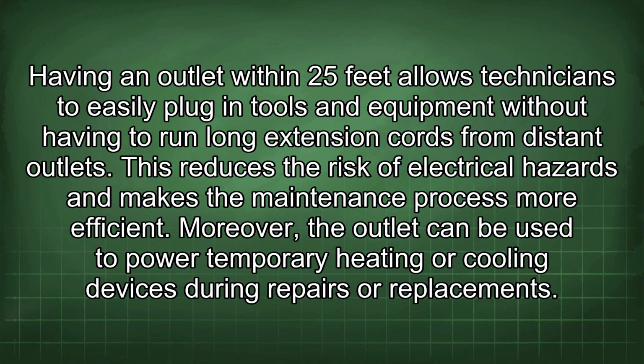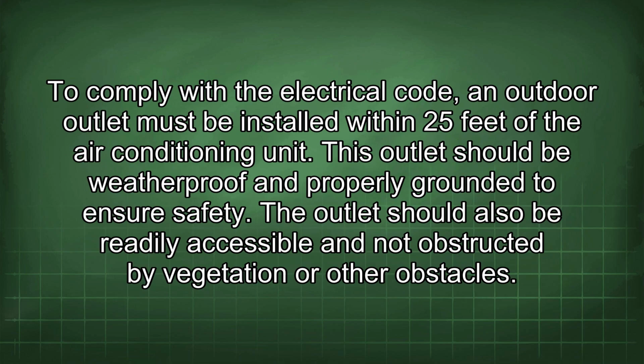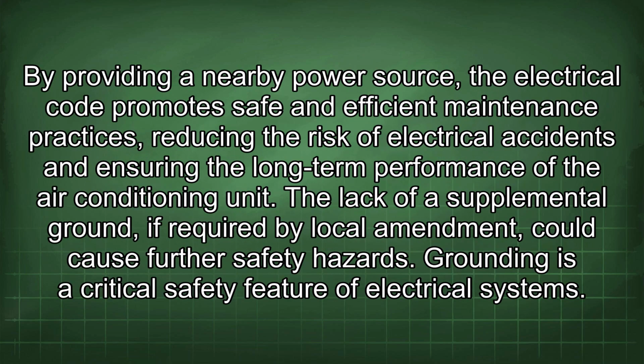Moreover, the outlet can be used to power temporary heating or cooling devices during repairs or replacements. To comply with the electrical code, an outdoor outlet must be installed within 25 feet of the air conditioning unit. This outlet should be weatherproof and properly grounded to ensure safety. The outlet should also be readily accessible and not obstructed by vegetation or other obstacles. By providing a nearby power source, the electrical code promotes safe and efficient maintenance practices, reducing the risk of electrical accidents and ensuring the long-term performance of the air conditioning unit.